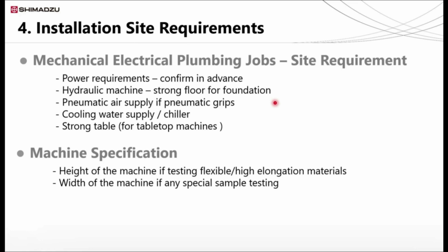Mechanical, electrical, and plumbing jobs are basically the customer's responsibility unless otherwise agreed earlier with the supplier. Power requirement: confirm the power requirement in advance. Sometimes it might need high rating breakers or some special power requirement. Sometimes step up or step down transformers are needed according to your country's voltage and power specification. So discuss this with the supplier and make sure the required power is available for smooth installation.